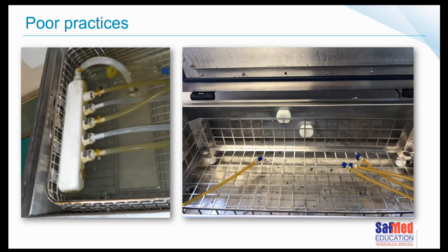And you can see the different tubing. So 2 had been replaced, 2 of them were newer, 3 of them were a lot older and that odd yellowy color. I don't know if that was just the material that had changed color because it was now brittle and old, or if there was actual fungal growth in that tubing as well. So that's why we please need to follow the instructions, read the manual, get the manual if you don't have one, so that you can properly disinfect and decontaminate your ultrasonic cleaner.